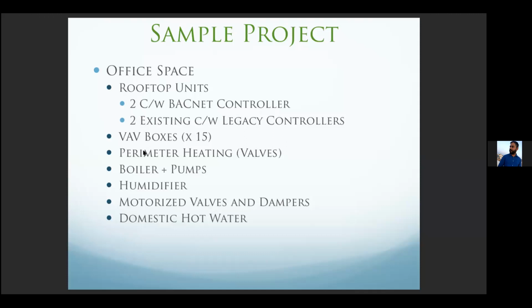Most of the times, you're able to find that one analog output or binary output, depending on what kind of control signal is required. But if not, then you can put on a little expansion module onto the VAV controller and just wire it up to that valve over there.